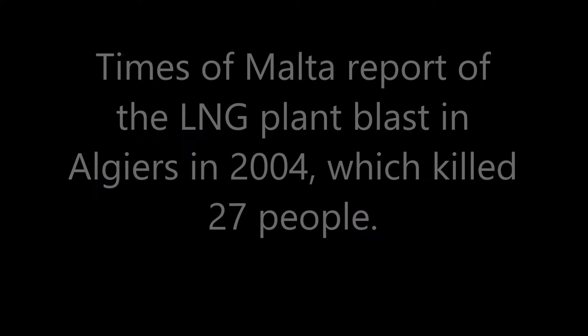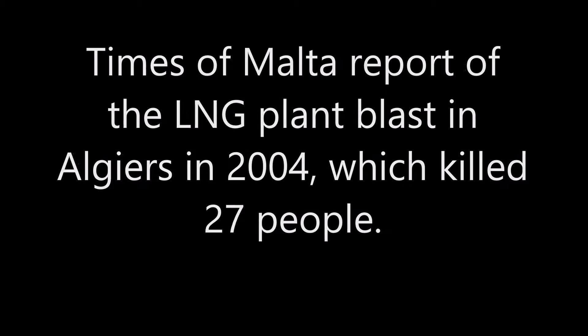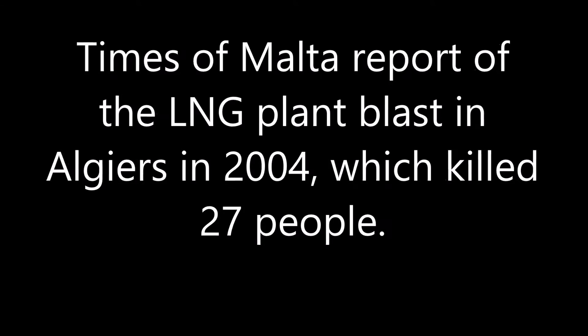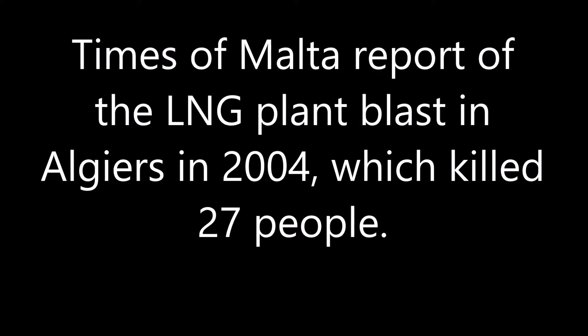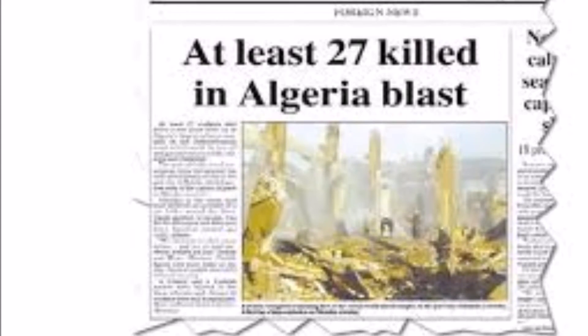In 2004, 27 people died and 74 were injured in an explosion at an LNG plant in Skikda, 500 km east of the Algerian capital. A report noted that the explosion was the consequence of a catastrophic failure in one of the cold boxes of Unit 40, which led to a vapor cloud explosion of either LNG or refrigerant.